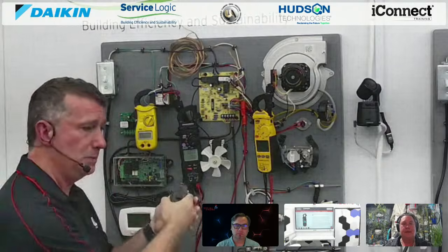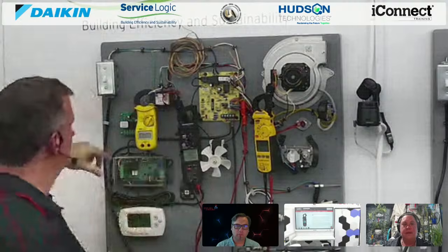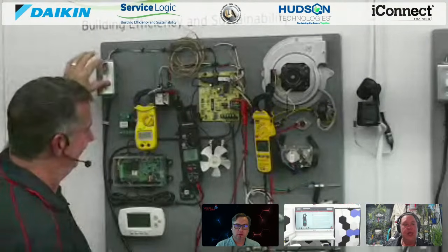So now we're going to show that same function. Maybe I've been chasing this voltage and spent the last 2 hours trying to find where it's coming from, because I've got a problem in my equipment - maybe a bad contact or a bad coil giving me this additional voltage I'm picking up on my meter. But is it real voltage? Now I can go to Low Z, so if it's just voltage that's been induced on our wiring, we put a small load on it and see if we can bleed that off. Ready to try it again? I'm ready.